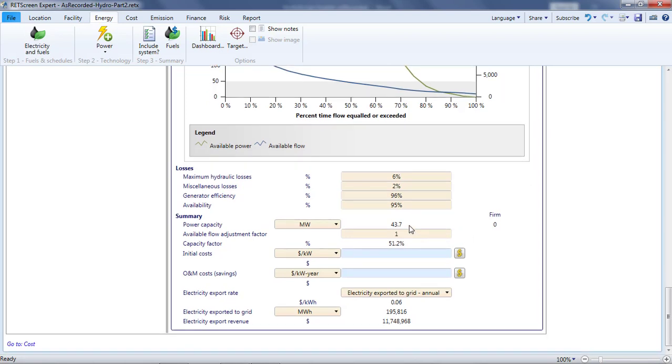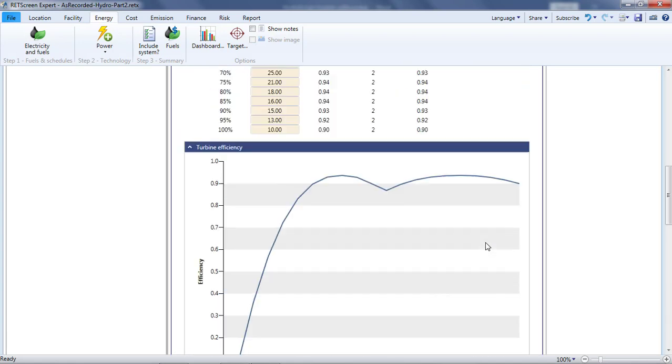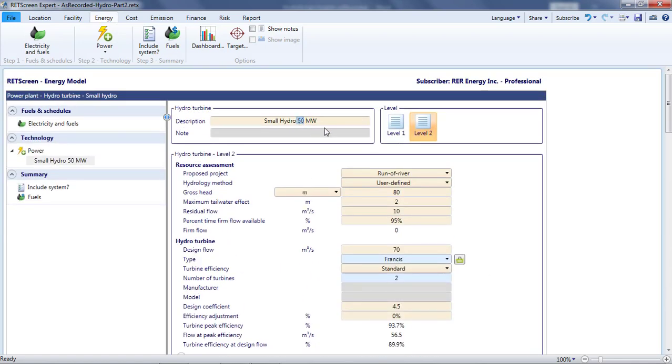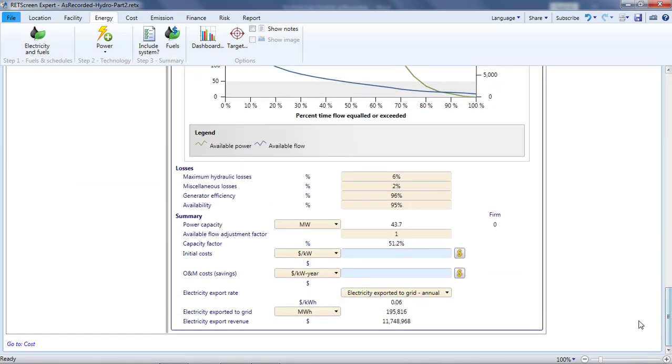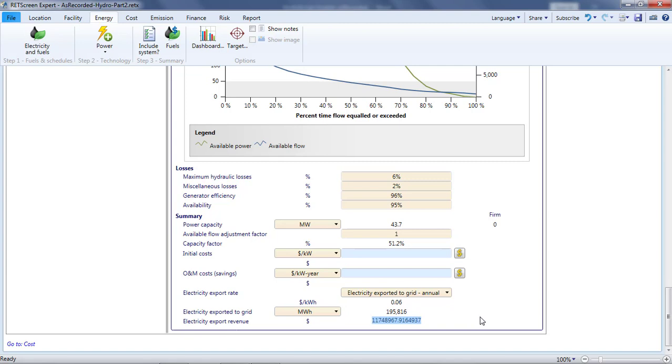The summary section gives me useful information. First, it shows that the capacity of my project is not 50 MW, but rather 43.7 MW. I'll update the project description with this number. It turns out that I was lucky with my 50% guess for the capacity factor. RETScreen calculates that it will be 51%. The project will export 196 GWh of electricity to the grid annually, worth 11.7 million Canadian dollars at 6 cents per kilowatt hour.